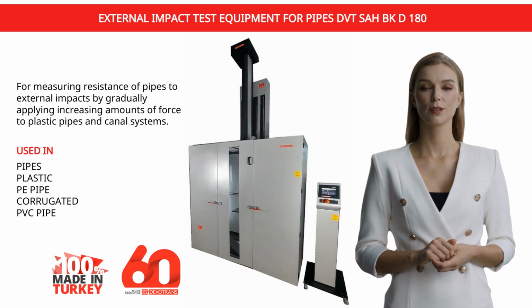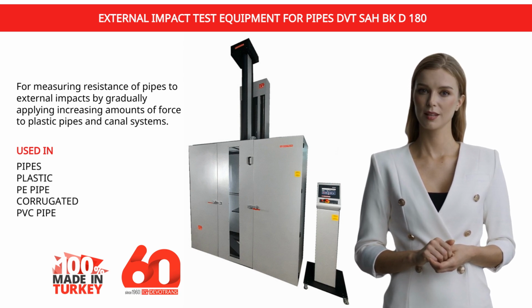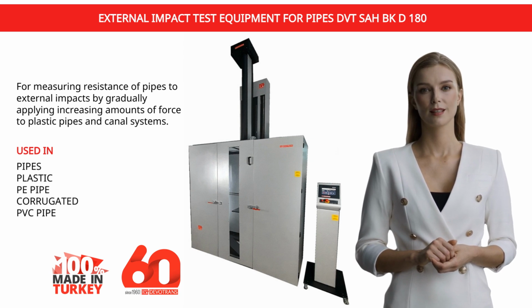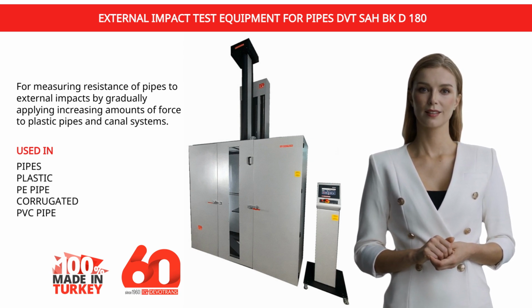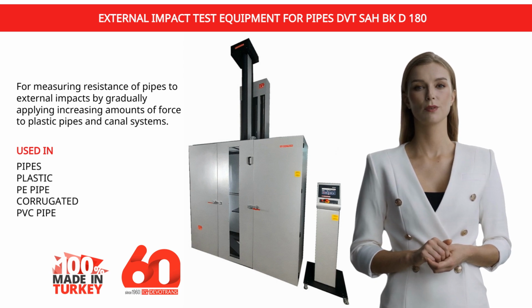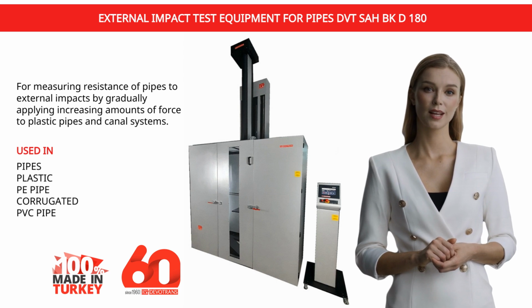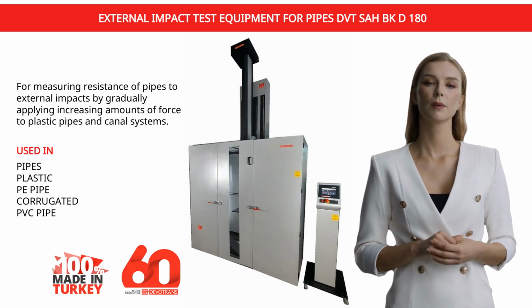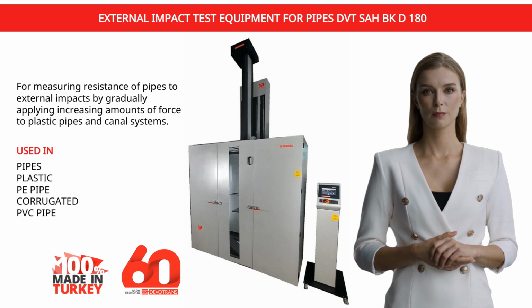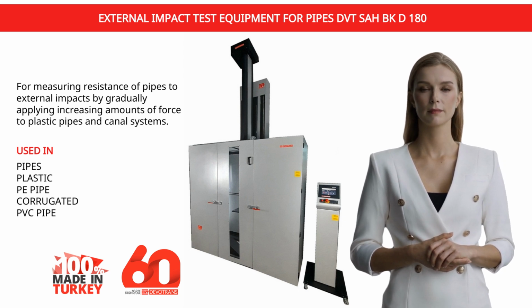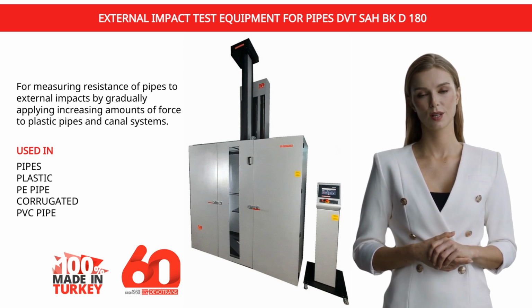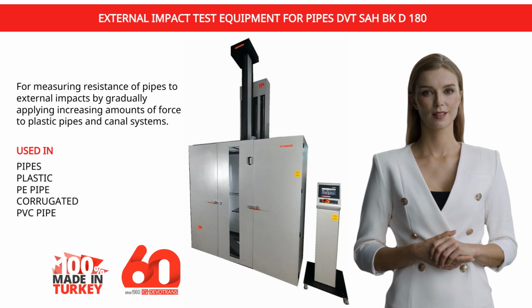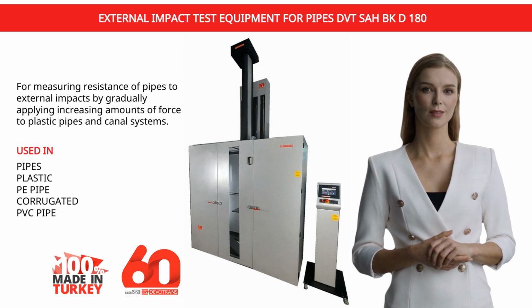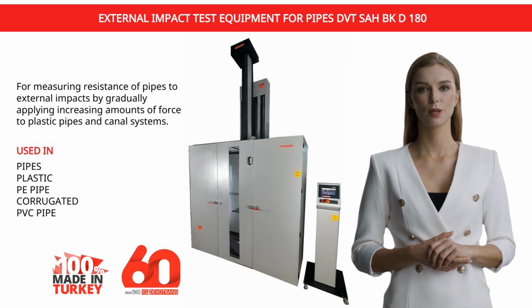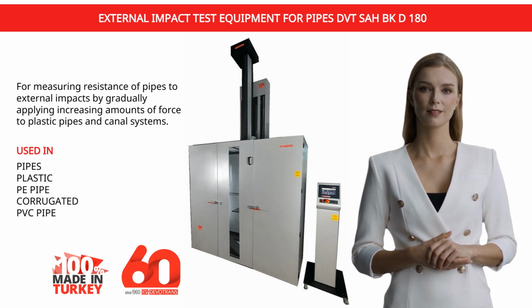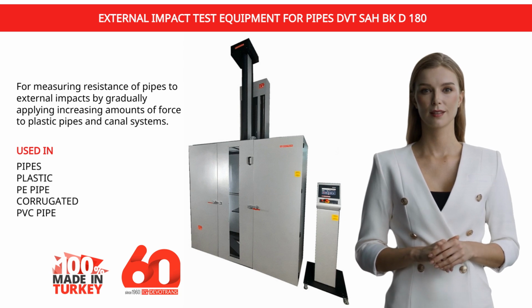4. Evaluation of results. Visual inspection. After the impact, the pipe is inspected for signs of cracking, breaking, piercing, or denting. If the pipe remains intact after the test, it is considered to have passed the impact resistance test. Crack and damage check. In some tests, it is checked whether the pipe shows only superficial cracking. The size, width, and depth of the cracks are also recorded. Breakage and deformation. If the pipe breaks or shows significant deformation, the material is considered to have failed the test. In this case, the material's mechanical strength is insufficient.